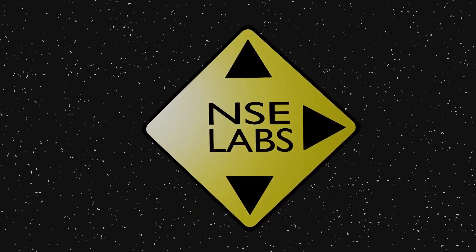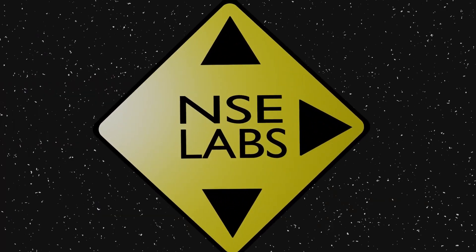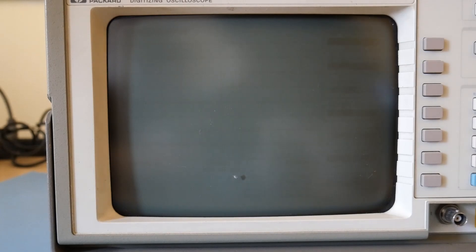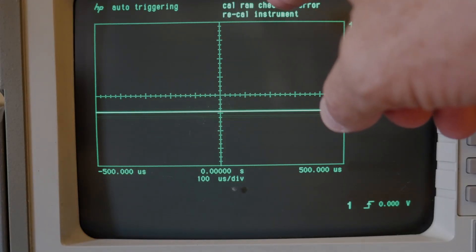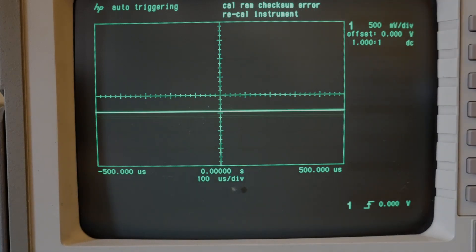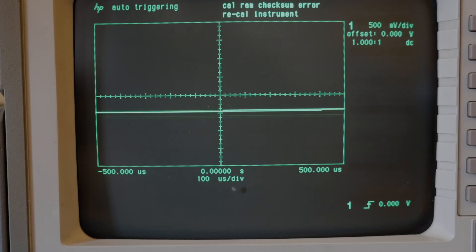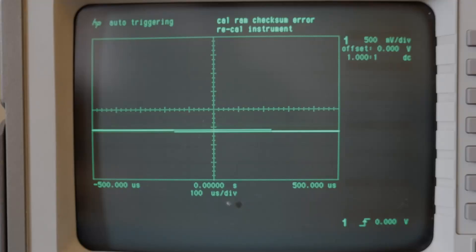So let's take a look and turn this on and see what happens. You can see in this part of the screen here it has a CalRAM checksum error recal instrument, and you also notice that the waveform is kind of going up and down there. Good news is it powers on and the screen works and all of that, but there's something to do with that Cal.